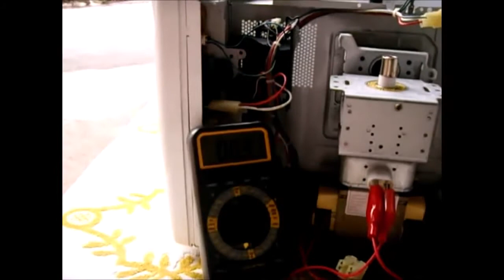Connect one probe to one terminal, the other to the other terminal, and you should have a very, very low reading like you see here. You don't want a dead short. You don't want to see 3 zeros, but you want to see anywhere from 0.1 to 0.3 in that range. That's a good one.